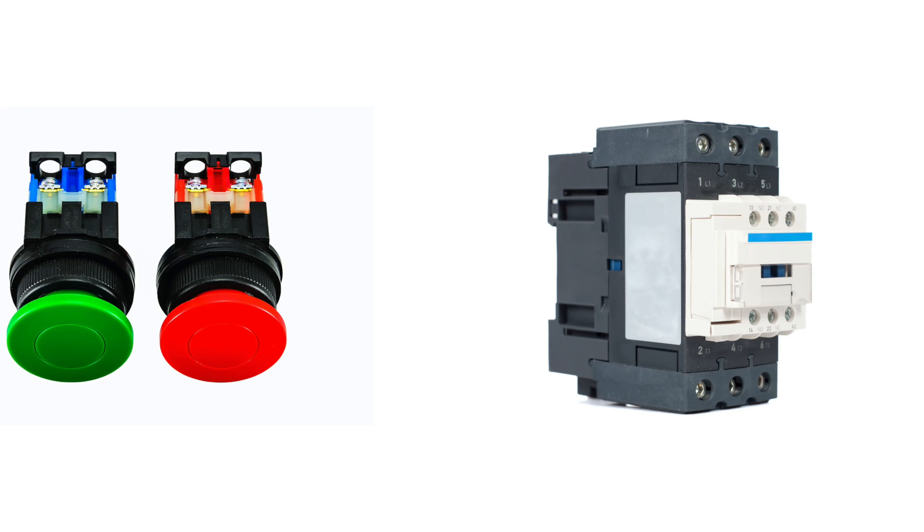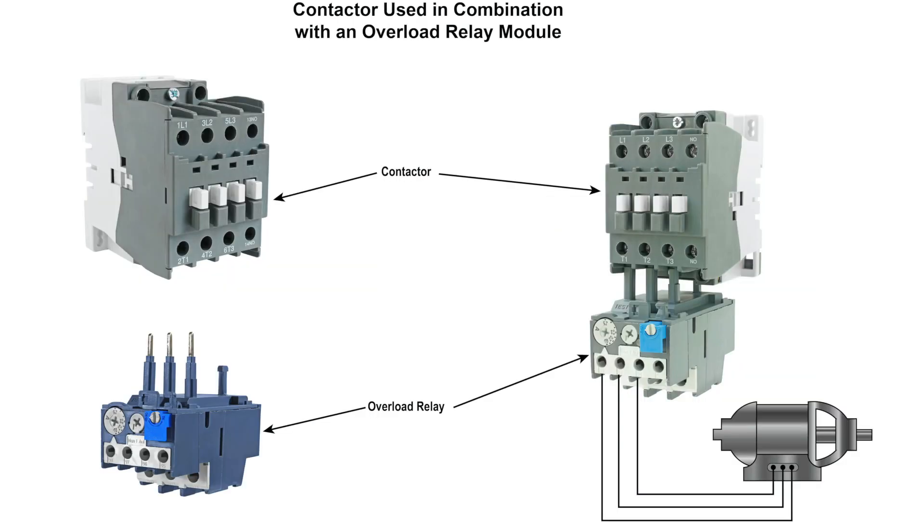Contactors are used in conjunction with pilot devices to automatically control high current loads. The pilot device, with limited current handling capacity, is used to control current to the contactor coil, which is used to switch heavier load currents. Another more common use for contactors is using them in conjunction with an overload relay assembly in an AC motor starter. The example provided shows a contactor used with an overload relay to switch a motor load.